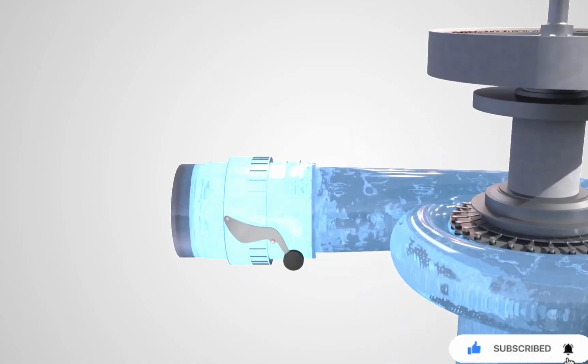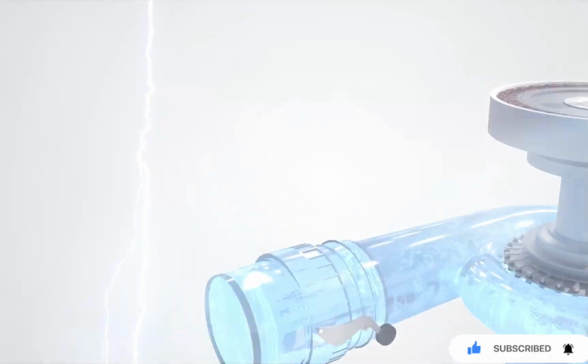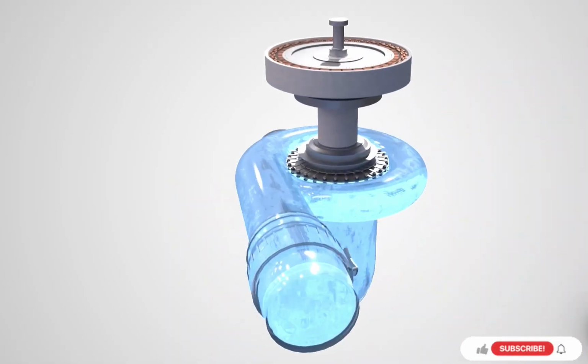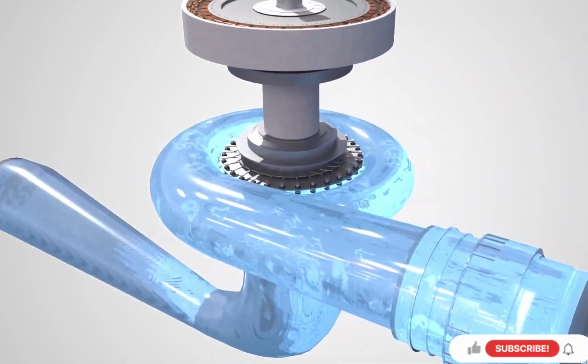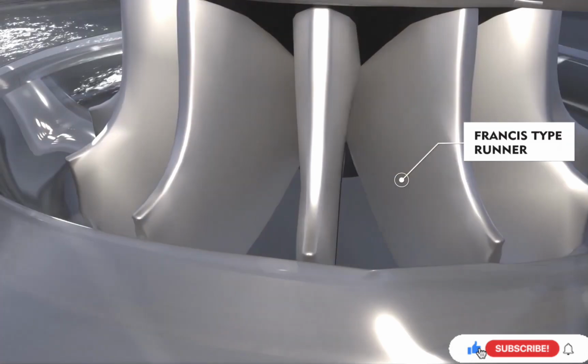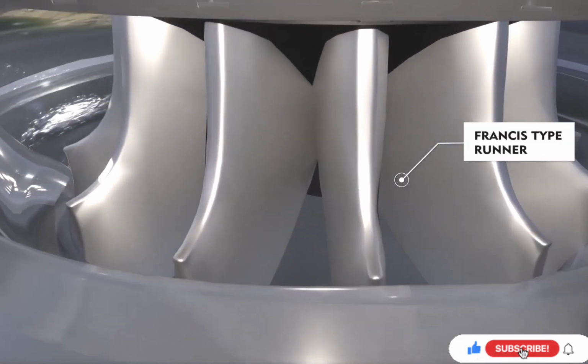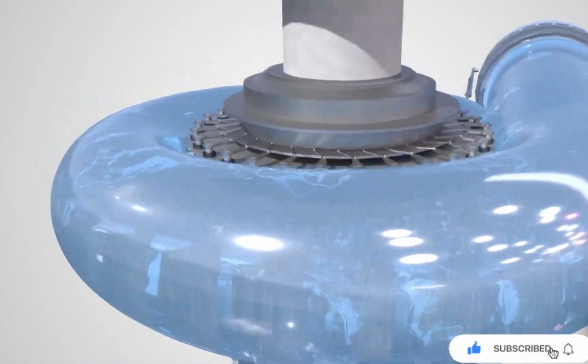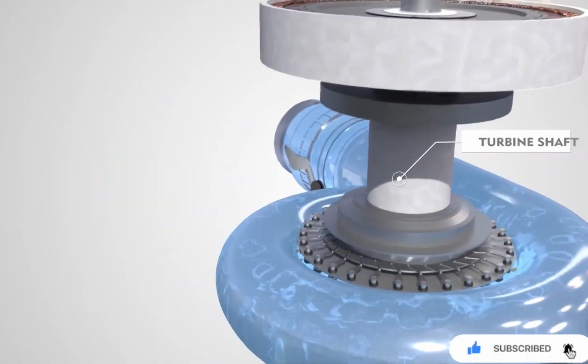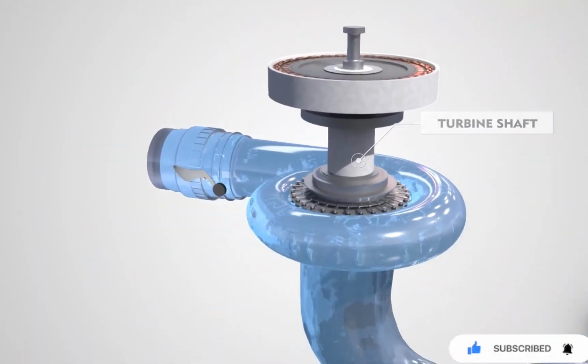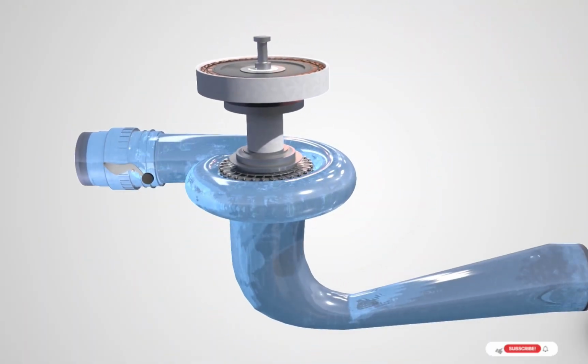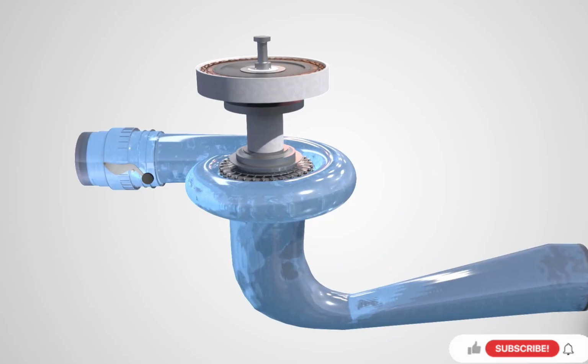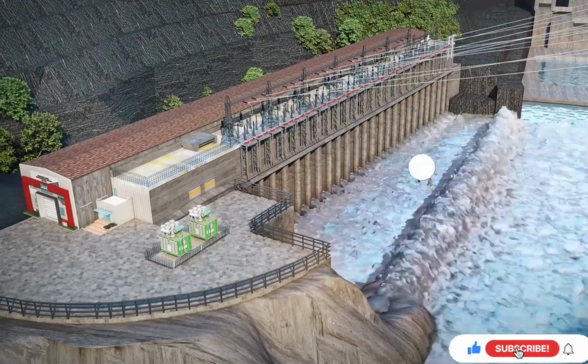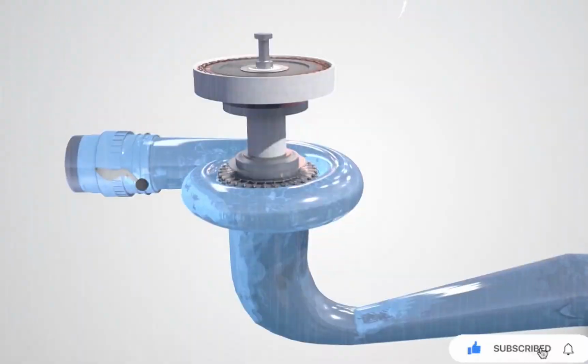When the main inlet valve opens, water starts to flow through spiral case, stay vanes, guide vanes and the Francis turbine runner, the heaviest turbine runner of the country, weighing 105 ton. The runner is coupled to the turbine shaft. Due to the water flow, the runner rotates, thus rotating the turbine shaft. Water after passing through the runner is channelized through the draft tube and TRC to exit into the tail pool.